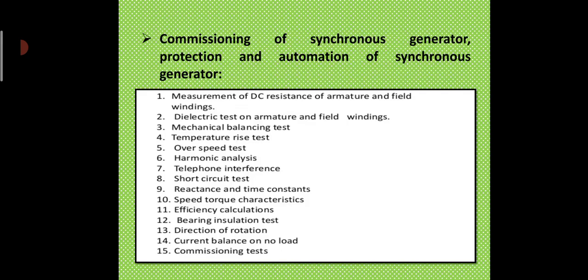Now, commissioning of synchronous generator, protections and automations of synchronous generator. In this case, a number of tests are included in this theory. First is measurement of DC resistance of armature and field windings. Dielectric test on armature and field windings, mechanical balancing test, temperature rise test, overspeed test, harmonic analysis, telephone interference, short circuit test, reactance and time constant, speed torque characteristic, efficiency calculations, bearing insulation test, direction of rotation, current balance on no load, and commissioning test.